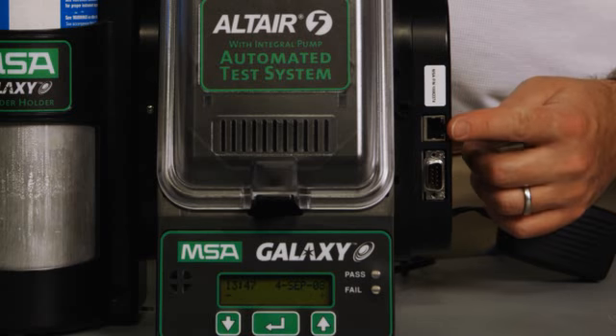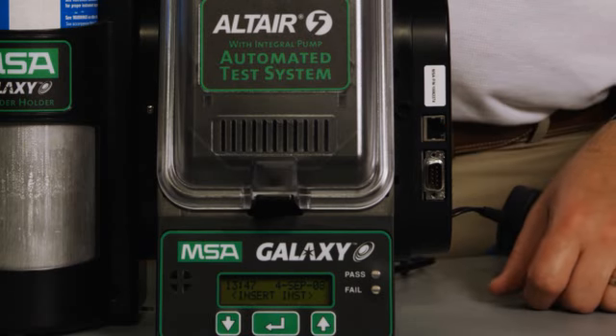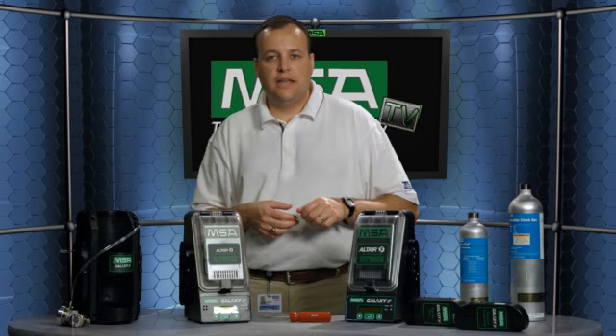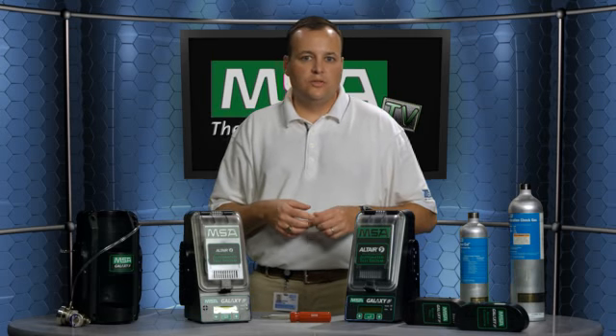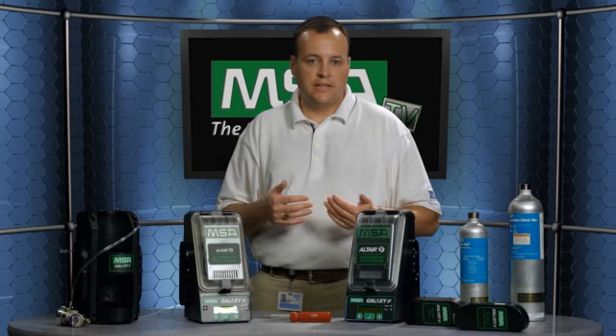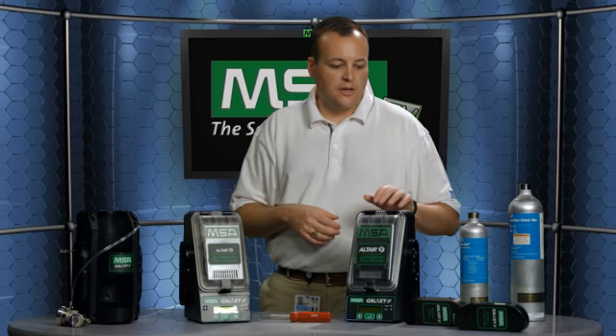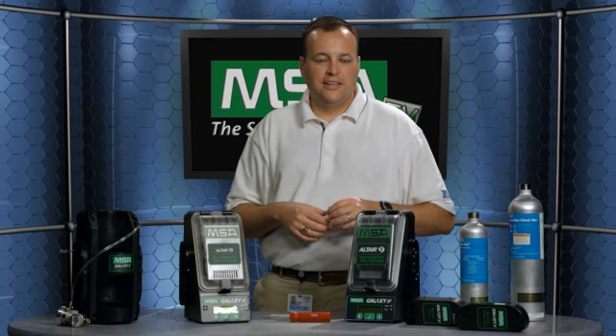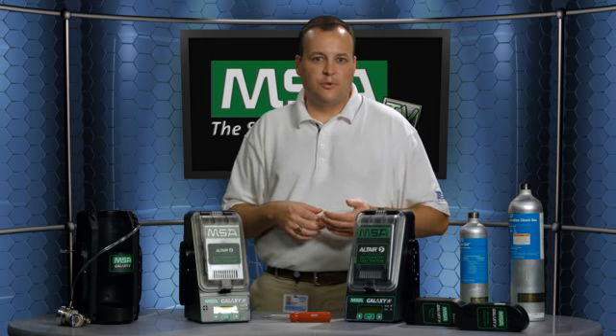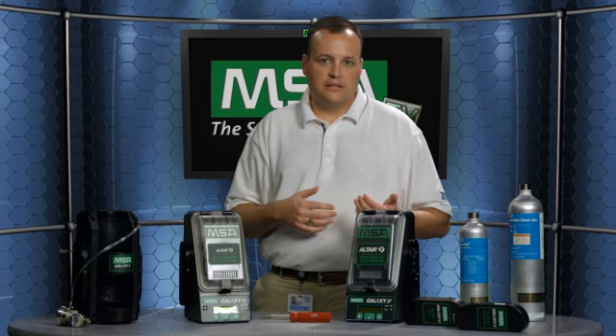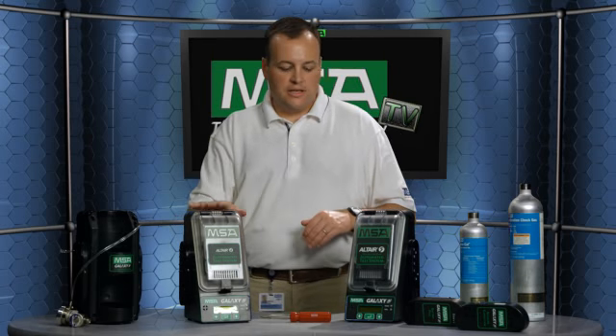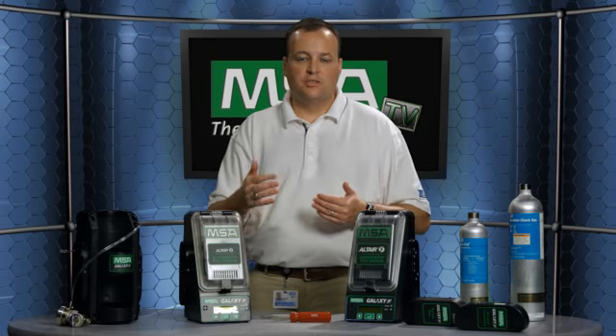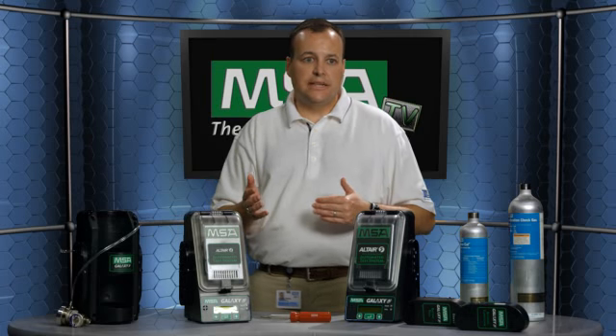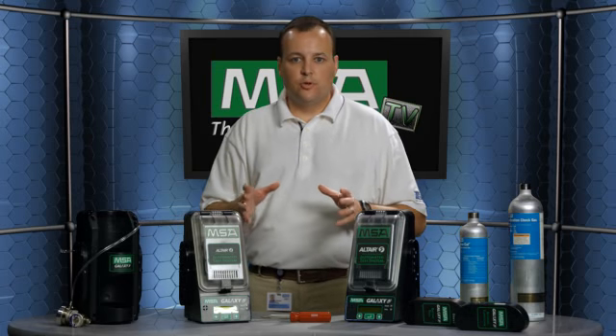There is a network, what's called a network connector accessory. That has a serial port connector, which will allow you to hook up a printer and get an immediate print receipt for your calibration or bump. It also has an Ethernet connector, which will allow you to do a wired network into a PC. So there's a lot of different ways through the accessories and through what's built in to get the record of a calibration or a bump, pass or fail, with a time and date stamp recorded, to have proof that an instrument was calibrated or bumped in a certain date and time.